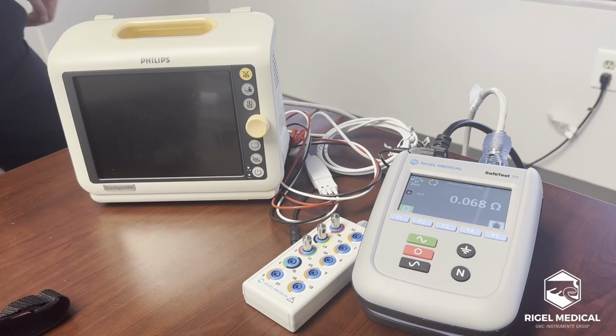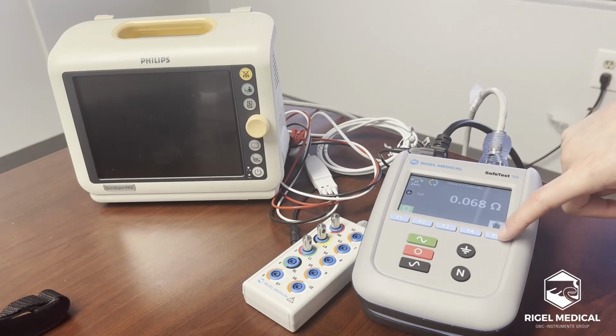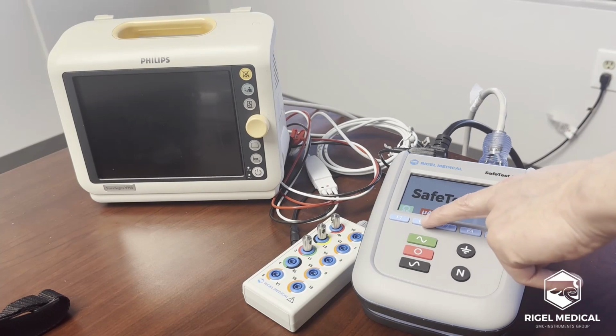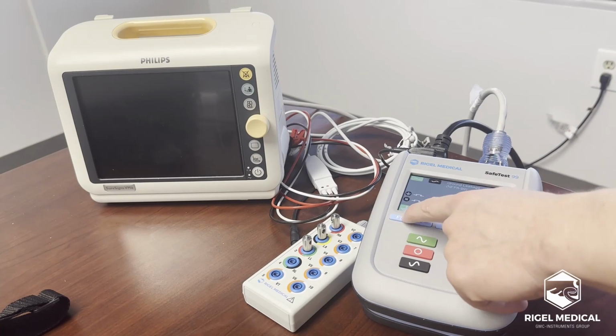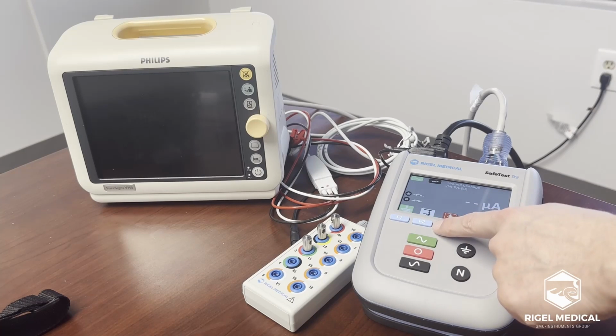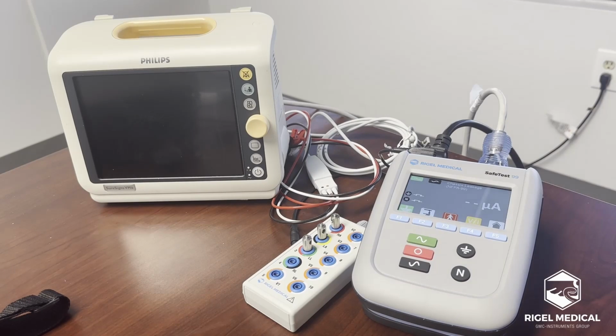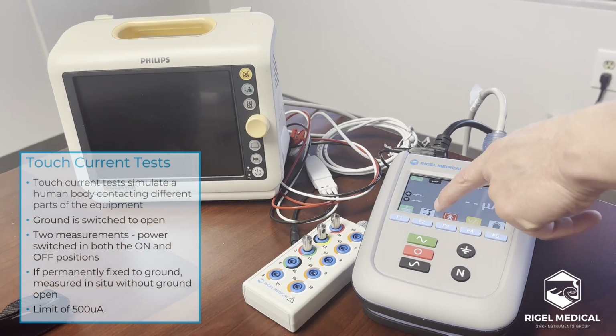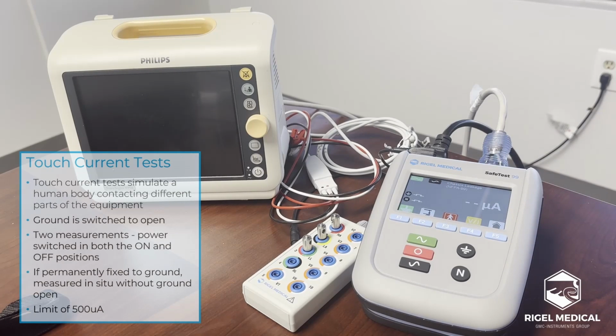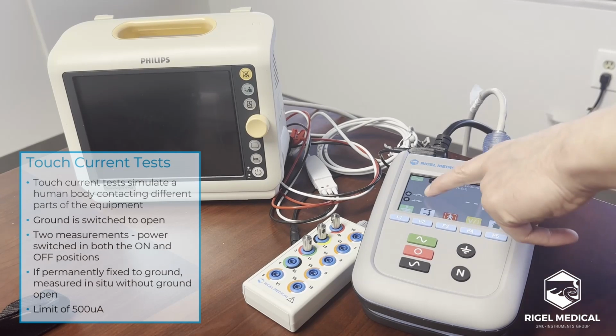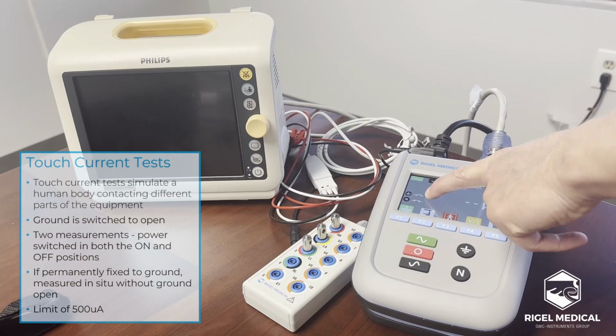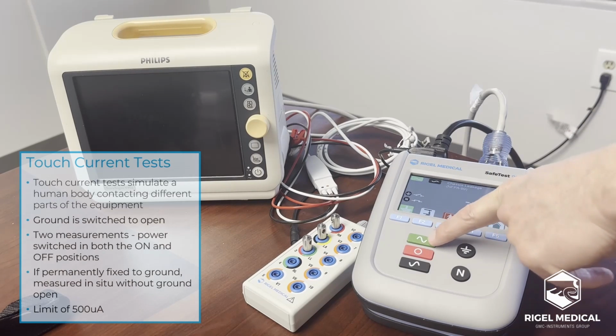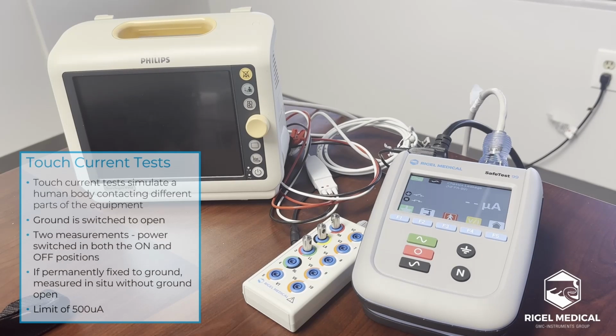equipment. So on the safety analyzer, hit the home button, and then we select F2, and that comes up with a list of the different leakage tests that the SafeTest 99 performs. Touch current is F2, select that, it's simulated by this touch symbol. And we see from the slide that it says ground switch is open, so we hit this button here. We can see that the relay switch is opened, and then we perform 2 measurements, power switching in both the on and off positions, and to activate the device we hit the green button, and that's now performing a touch leakage measurement.